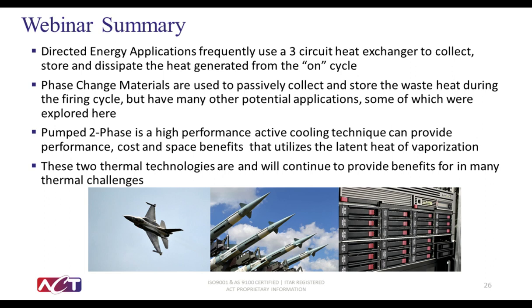In today's webinar, we reviewed the fundamentals of a three-circuit heat exchanger that is used in many directed energy applications to collect, store, and dissipate waste heat from the on cycle. We then reviewed in more detail two emerging technologies, PCM heat storage and pump two-phase cooling, that are being used to advance these directed energy thermal management solutions. PCM is used to passively collect and store waste heat so that it can be dissipated during the off cycle. Pump two-phase cooling is a high-performance active cooling system that utilizes latent heat of vaporization to efficiently remove large amounts of waste heat. These two thermal technologies are finding many applications both within and outside of directed energy applications, some of which were reviewed today.